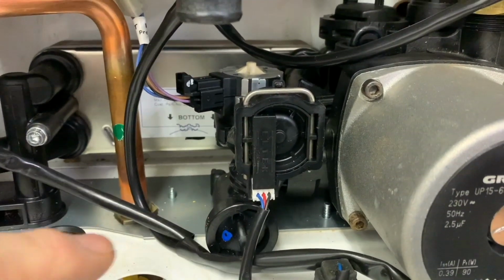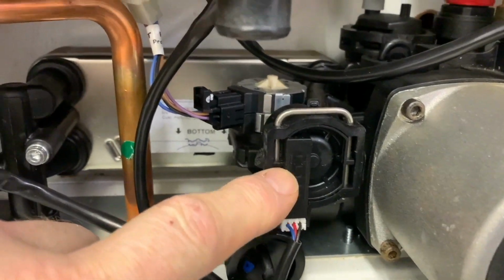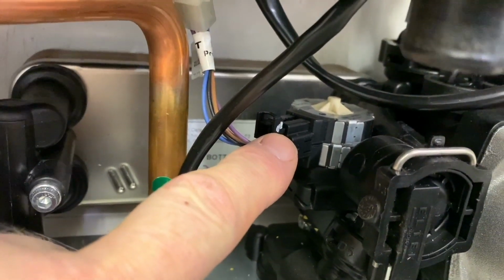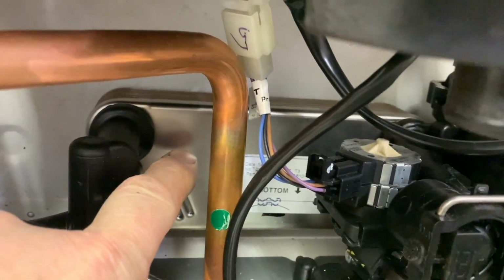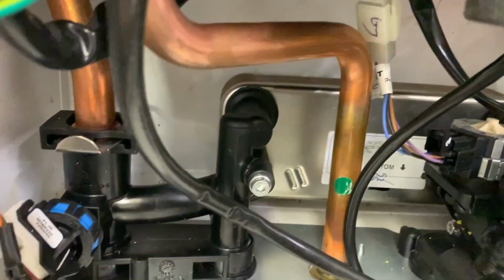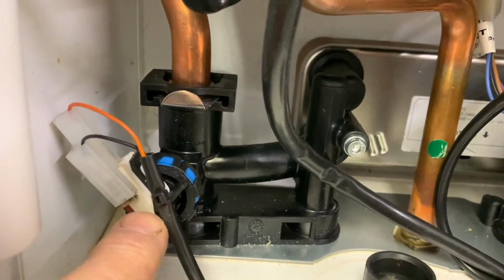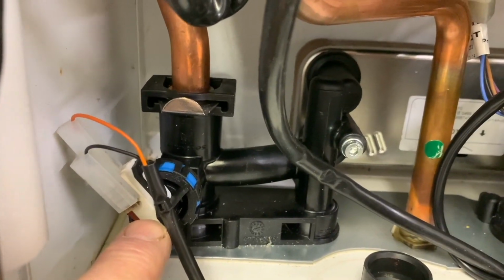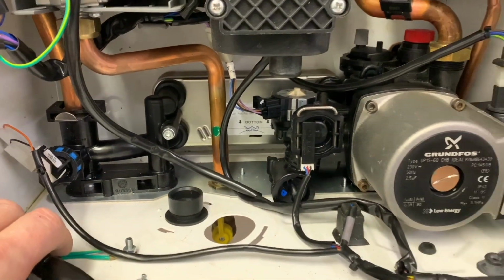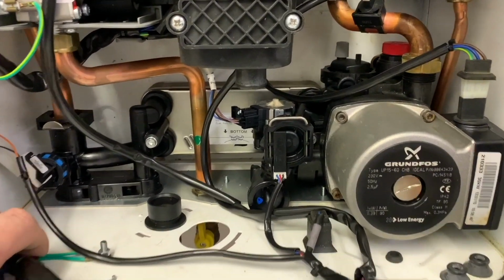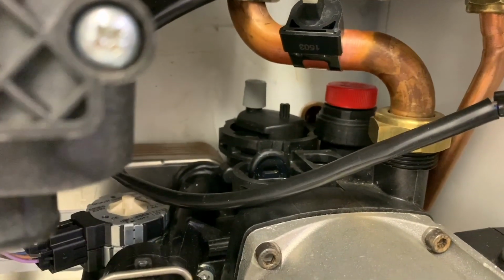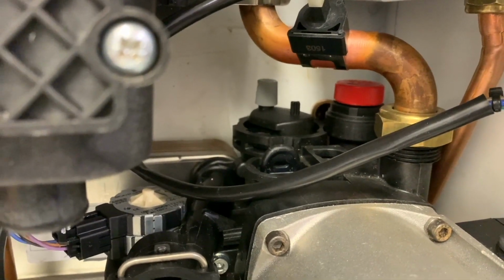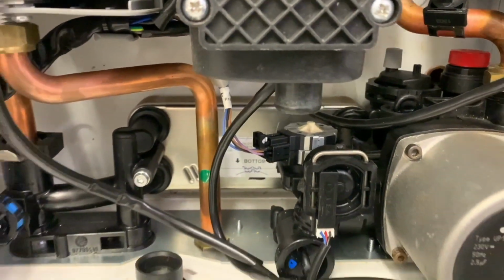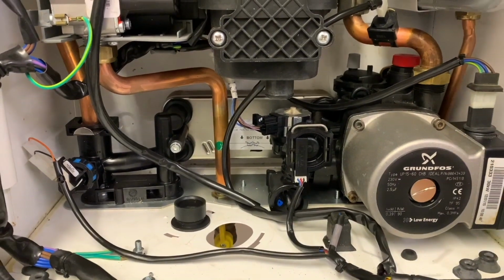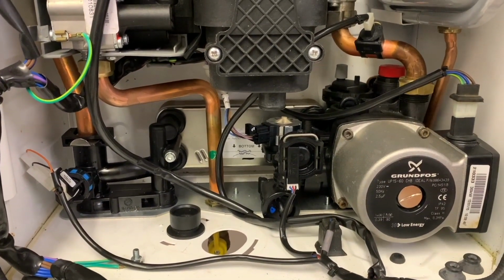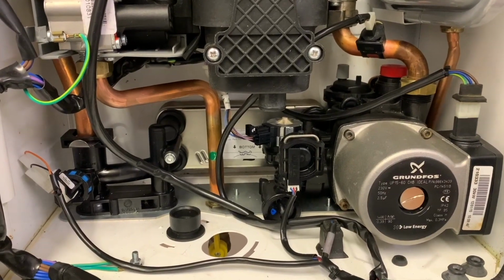So this is pretty much how it is now, and that is the diverter valve at the back. Again, we've got the plate-to-plate heat exchanger, and on the left side of the hydro block we've got the low water pressure sensor. So that's how the new one is. Again, you've got blow-off at the back, and you've got an automatic air vent. That's on the newer ones, and the brand new version is pretty much the same as this. Again, they've made some slight little alterations, but nothing spectacular.